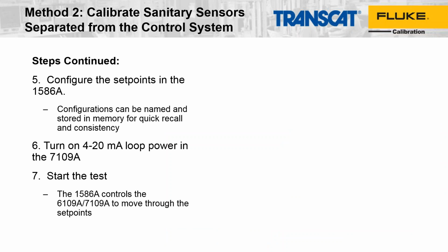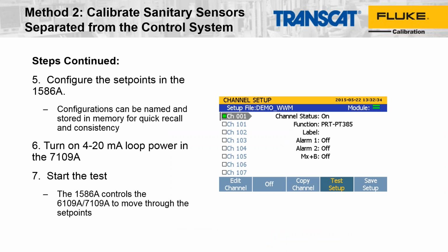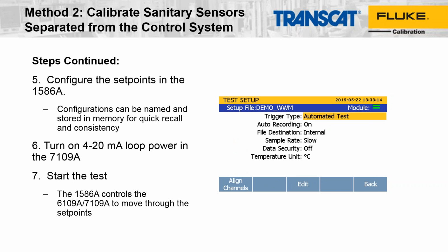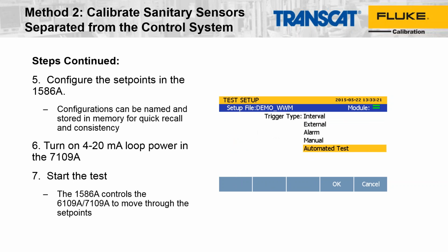Then we go over to the 1586A, and we're going to configure the channels that we need. In this case, we're going to have channels 1, 2, and 3 on the scanner configured. Once we have the channels configured, then we go to the automated test screen, and this is where we configure the test similarly like we already talked about in the 7109A. And this is just going through the menu of setting up the test.